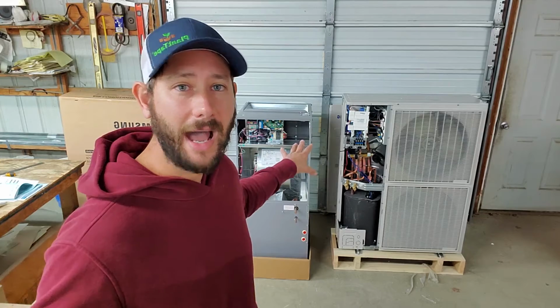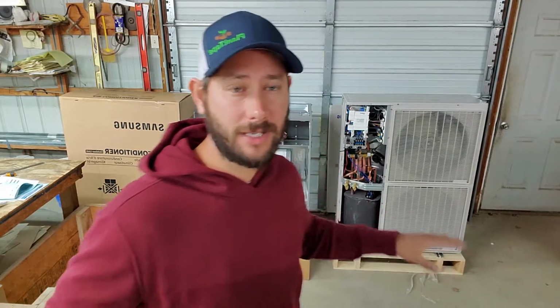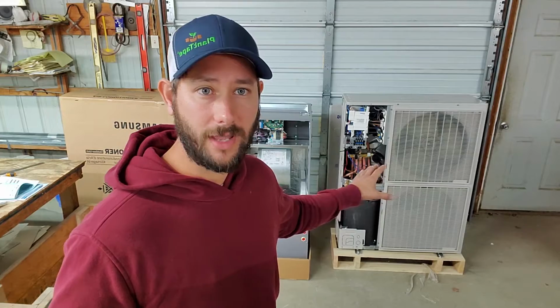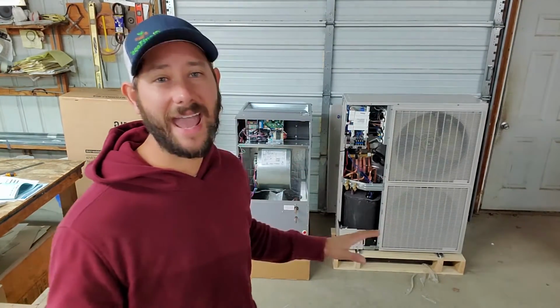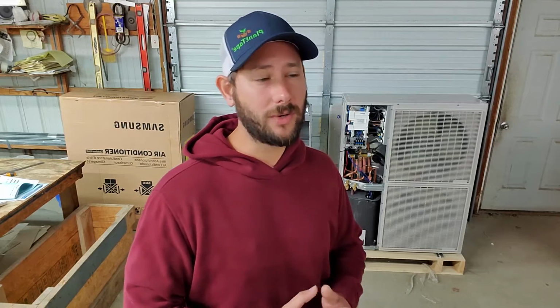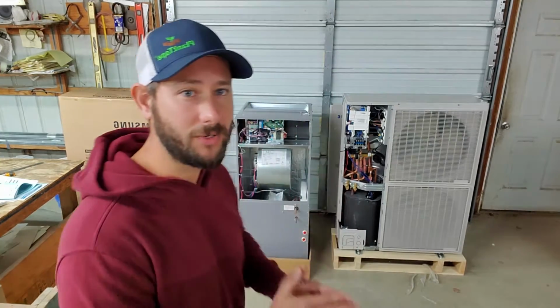And in this equipment, I only have to have heat strips as a backup, strictly emergency, because this equipment will actually work down, the operating temperatures exceed that of the conventional. You can work in 0-degree weather and still be somewhat efficient compared to the conventional where you can't gain heat from the outside air. So that's one thing I'd like to say about this equipment. It's fantastic when it comes to operating temperatures in the heating mode during the cold winter months. Now, if you go below -4, then you're going to derate, you're going to lose efficiency. But when you're in a mild climate, this equipment is really, really efficient and it's going to save you money. So we're producing really, really good heat.